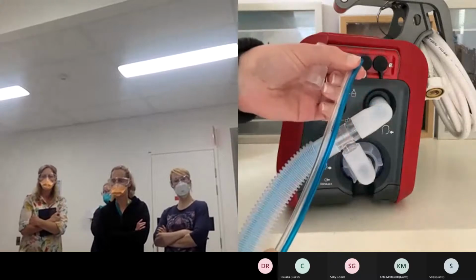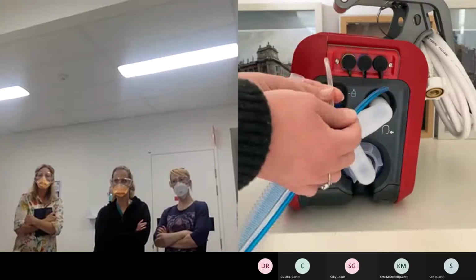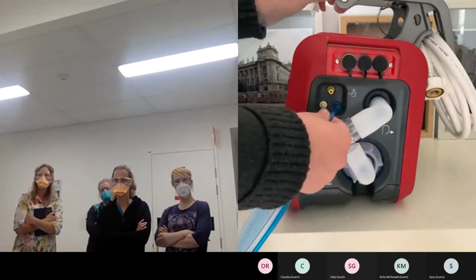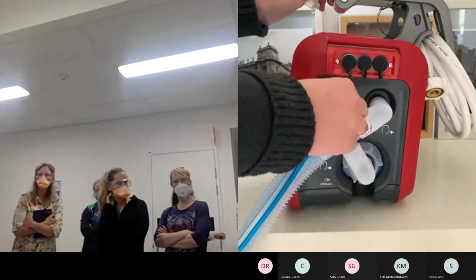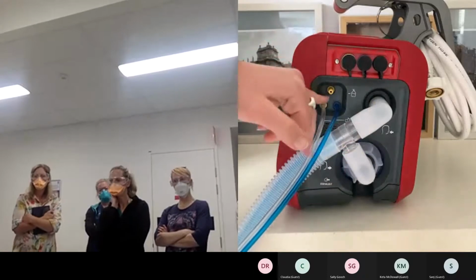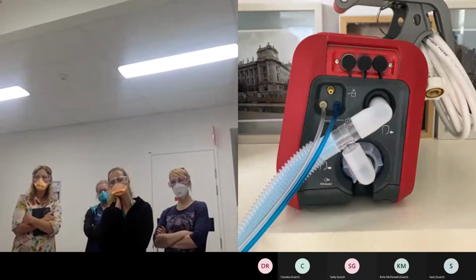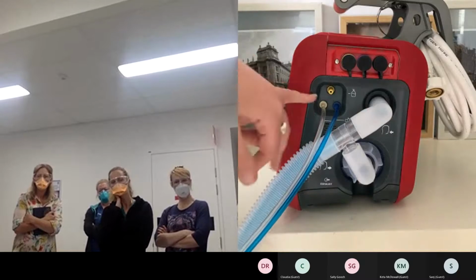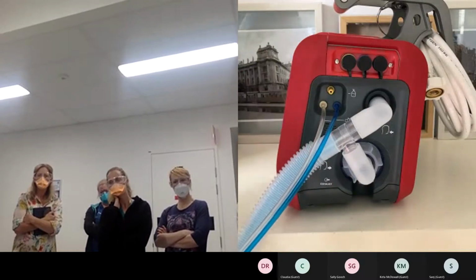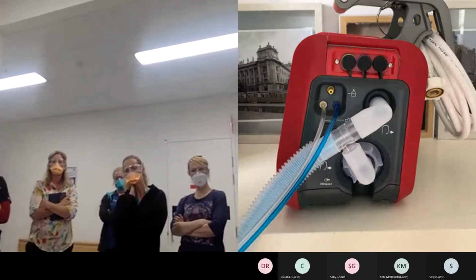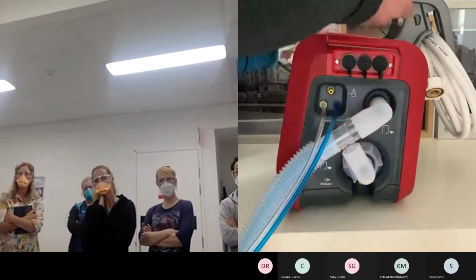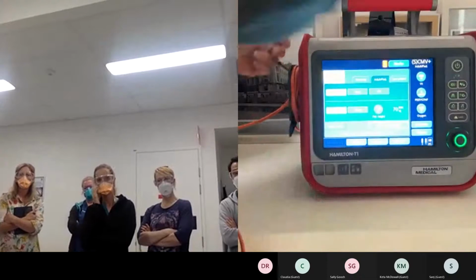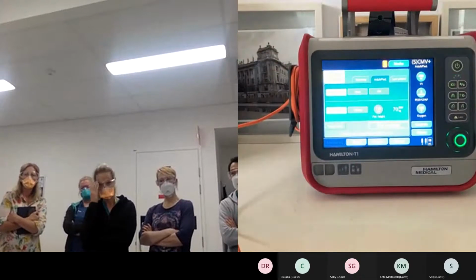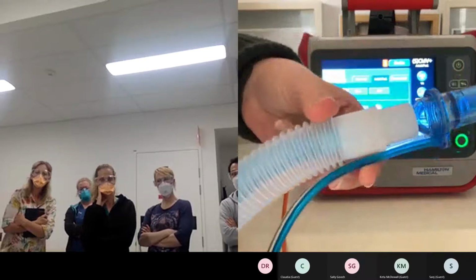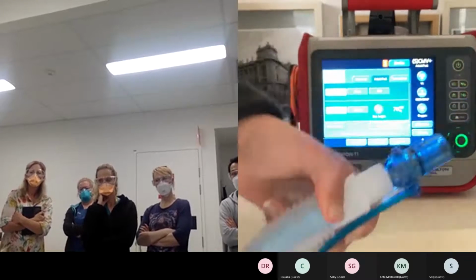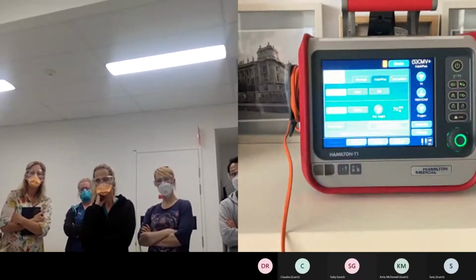Then you've got your flow sensor, and it comes with these two lines, and you've just got to separate them apart and then line them up white to white and blue to blue. The yellow port that you've got here is for a pneumatic nebulizer, so we can run a nebulizer through the machine as well. Okay, but that's the circuit setup. The flow sensor will already be up and connected up to the tubing, so you don't need to worry about anything on that front of it.